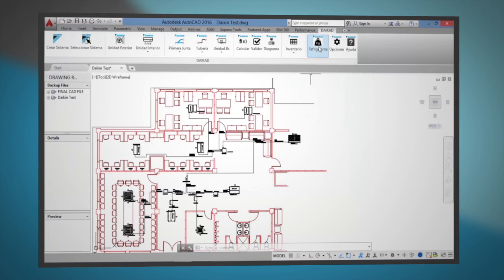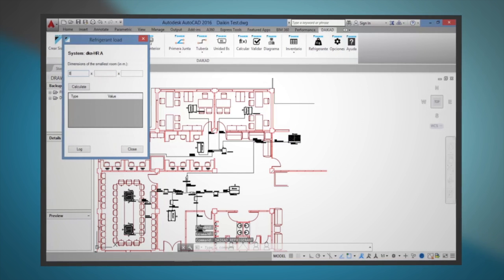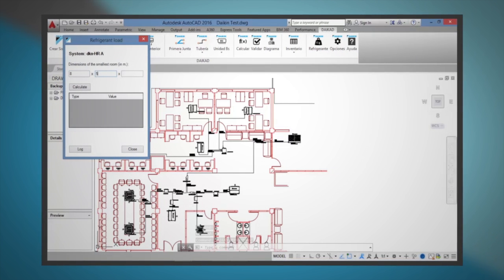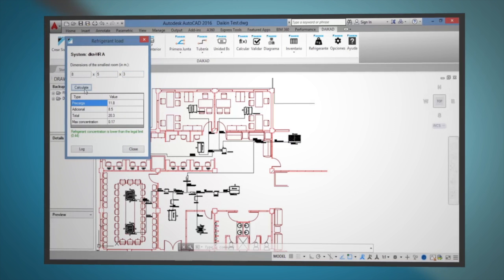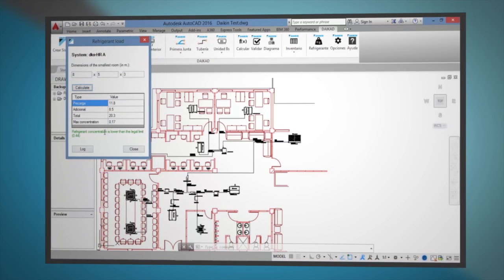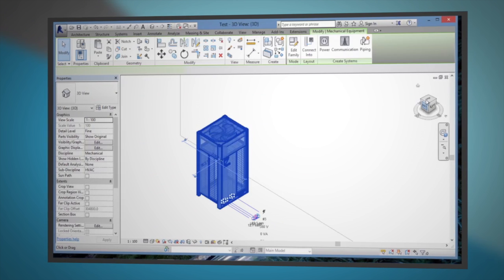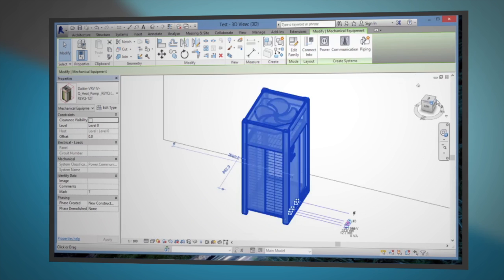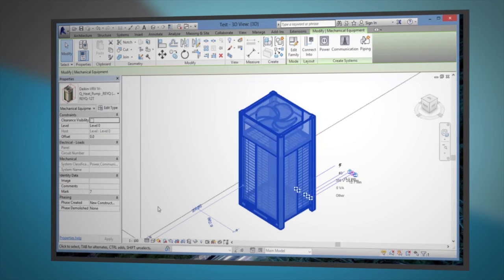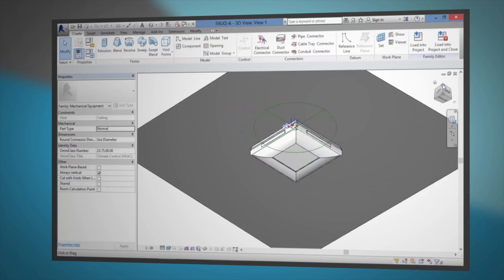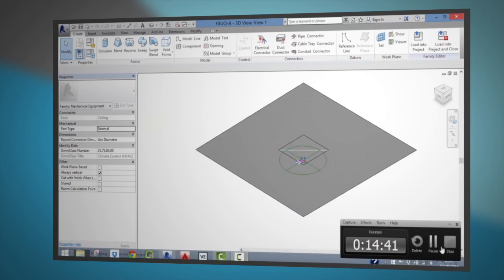You can also calculate how much additional refrigerant will be required on site. You can even check compliance with EN 378 to ensure that for hotel projects, for example, you can eliminate the need for expensive leak detection. This software is also available for Revit and will work in a similar way. Objects can be simply dropped into place and then connected with pipework. All of the calculations are made for the pipework sizes and checks are performed to ensure the system complies with the design criteria.